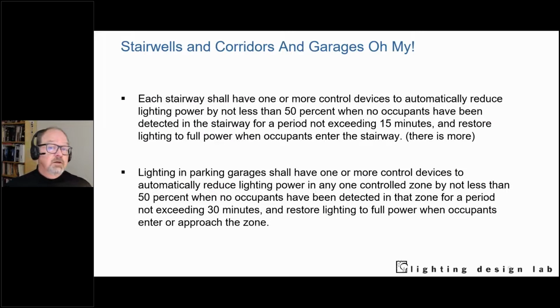There are some specialty cases, in particular stairwells, corridors, and garages, where you need to be able to dim the lighting accordingly and have an occupancy sensor so that when you walk into, say, a stairwell, the lights go up. This is nothing new—there have been light fixtures marketed by manufacturers for at least 20 years that automate this process, early luminaire level lighting controls with sensors built in, so that when they sense people in the stairwell, they dim up from their, say, 20% light output.